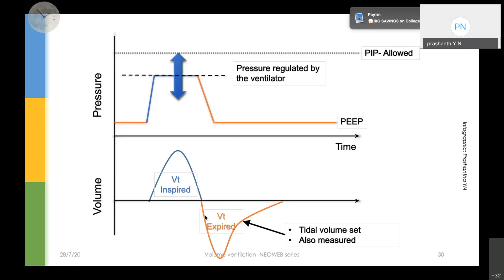All right. So here, we are going to measure how much is expired by looking at the area under this curve. The microprocessor will look at the area under this curve to see how much volume is expired. So what it does is, if you can see this, there is an inspiration. The pressure is increasing here, which is driving the volume into the baby's lungs. This is your inspiratory tidal volume. After it stops, there is your expiration. So I want this ventilator to deliver a tidal volume of 4. When I say I want to deliver a tidal volume of 4, I'm telling the ventilator that this orange one has to be 4 ml.